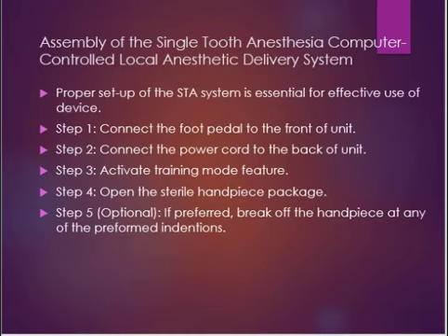This next part is going to be assembly of the single tooth anesthesia, STA, computer controlled local anesthetic delivery system. You need to have proper setup of the system so that it's effective for using the device. Step 1 would be connect the foot pedal to the front of the unit. Step 2, connect the power cord to the back of the unit. Step 3, activate training mode feature. Step 4, open the sterile handpiece package.